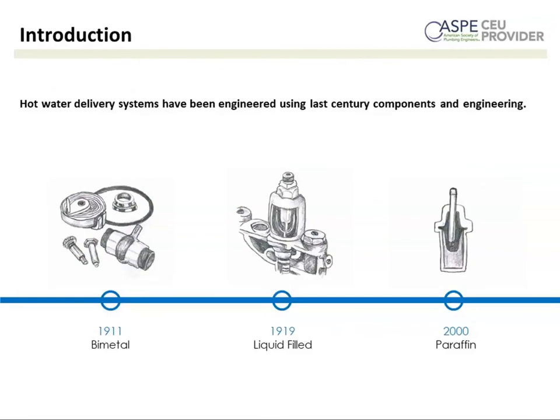So if we take a step back and look at how we've been doing this, particularly at the point of source, the point of distribution, we've been managing water temperature, and still do effectively, for quite a while, right? If you look at the thermostatic elements incorporated today in bigger mixing valves and smaller ones too, there's bimetal, there's liquid filled, which might be like ether, and then more recently paraffin, which has been fairly common in smaller mixing valves but over recent years has been pioneered into larger master mixing type products and high-low systems. So not a lot has really changed up until recently.